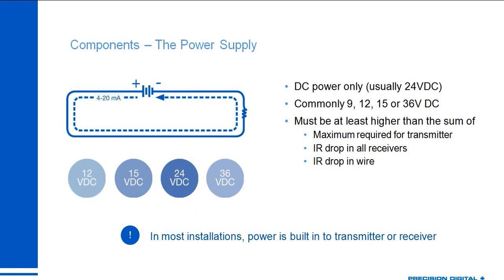Looking at the scaling example: a level transmitter designed for 100 feet outputs 4mA at 0 feet and 20mA at 100 feet. At 50 feet it outputs 12mA. The transmitter regulates the current in the loop; the power supply provides the voltage to make that current possible — V = IR. This is always a DC power supply. In most process applications, people use 24 volts because it's the most common, though you can find 9, 12, 15, and 36 volt supplies. The power supply provides the DC voltage; it doesn't regulate the current — that's the transmitter's job.